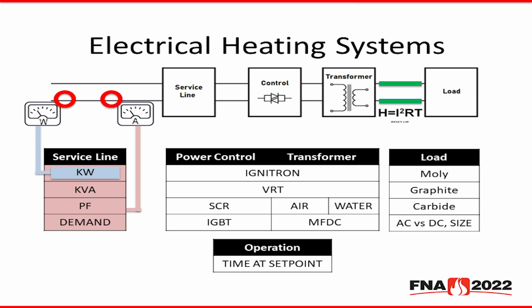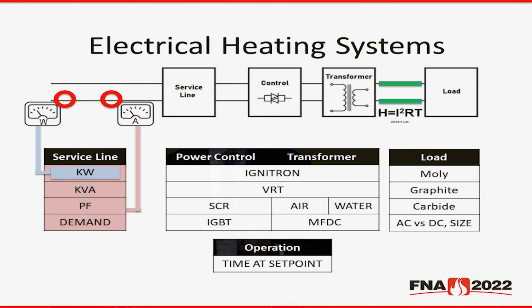Historically, there are ignitron tubes or thyristors. These are just rectifiers that control power to an application. These were used prominently in the 1930s and 40s. And then came the VRT, or variable reactance transformer. A variable reactance transformer is actually a power controller and transformer in one. There's a DC saturating coil that saturates or desaturates the core of a transformer to control power to an application. And then we have the common day SCR and IGBT control types. SCR stands for silicon controlled rectifier, and IGBT stands for insulated gate bipolar transistor.